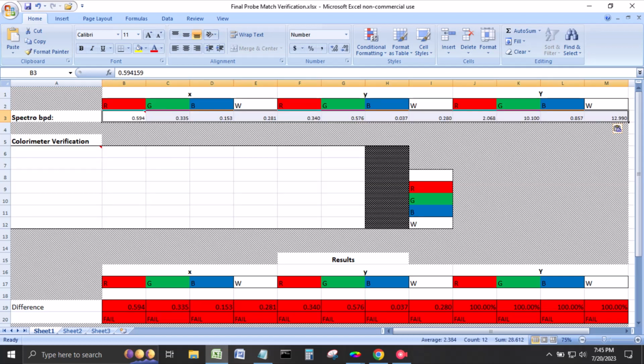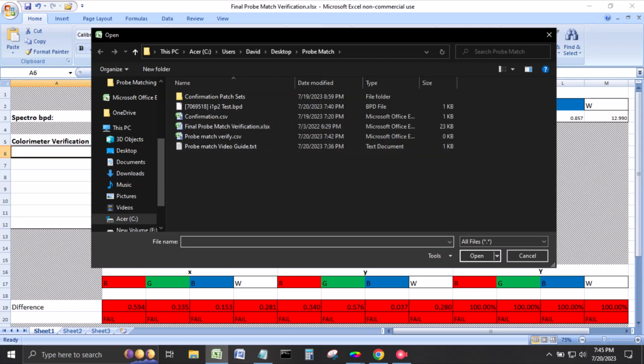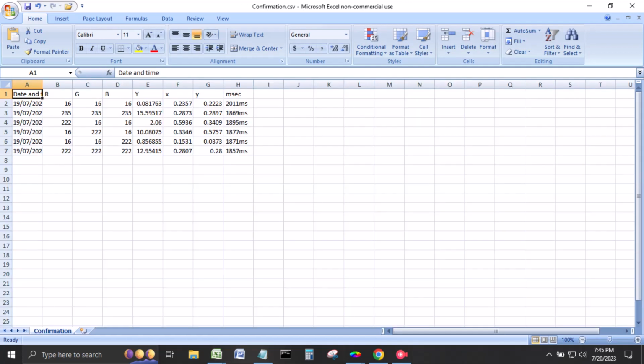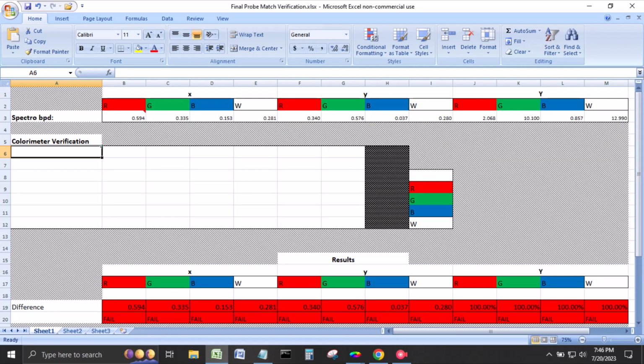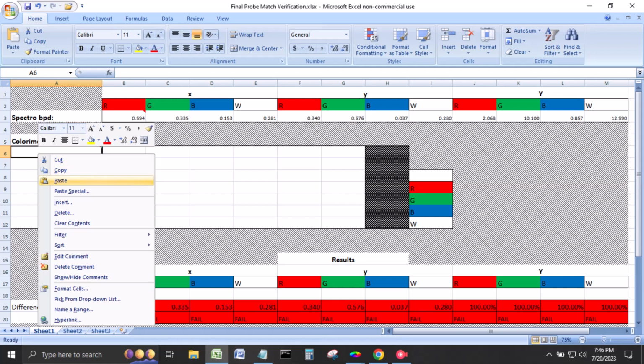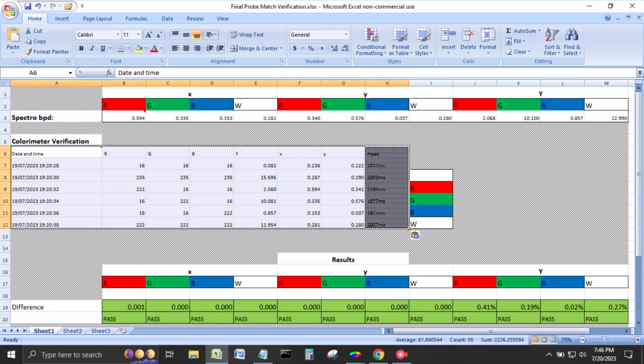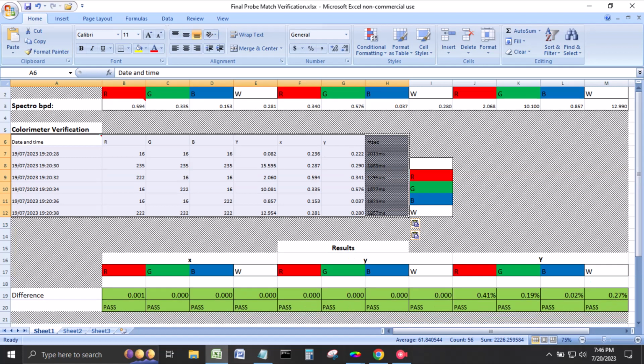Awesome. Now we need to get those measurements from our probe match colorimeter. To do that, just go back to our probe match folder, and we're going to find the confirmation.csv we made and choose Open. Here, you're going to leave your cursor in box A1, and then you're going to hold the Shift key again and select H7 down here in the bottom. Right click, copy all those values, close this. Then you're going to put your cursor in cell A6 of your verification, and you're going to paste those values. The spreadsheet is made so that it will compare the measurements in the correct places between your spectro and your colorimeter, and down here in the bottom you will get the results.